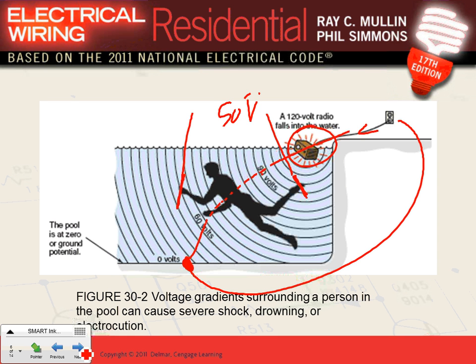Let me tell you one thing very similar to this, guys, in a substation. If you work for Excel at a substation, if you're walking in a high voltage substation, you guys have seen these big substations outdoors. You walk in the substation, and there's a ground fault while you are walking inside. There are a lot of ways to protect you from this, but while you're walking, the current will go through the ground. When the current goes through the ground, guys, there will be a voltage difference because of the impedance of the ground between foot 1 and foot 2, your two feet.